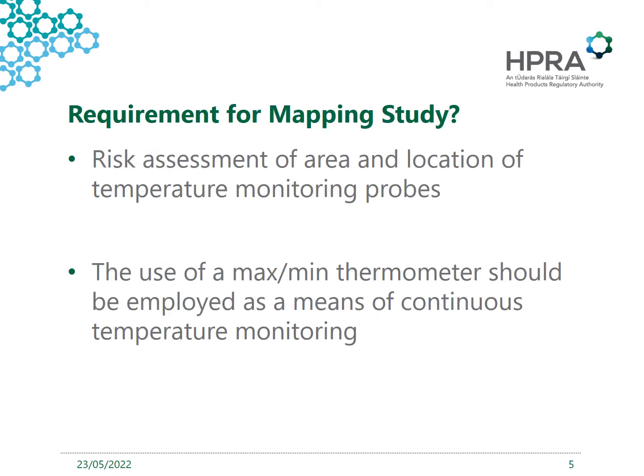The first step in the process is to identify the requirement for a mapping study. In my experience, a mapping study is required in the majority of cases. However, for significantly small spaces used for the storage of low-risk medicinal products, it may be appropriate to solely conduct a risk assessment. In this instance, it's important the company document its evaluation of the proposed storage area and identify any risks within its assessment.